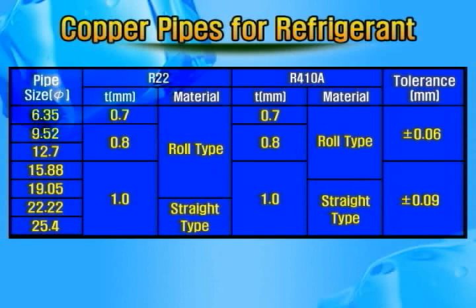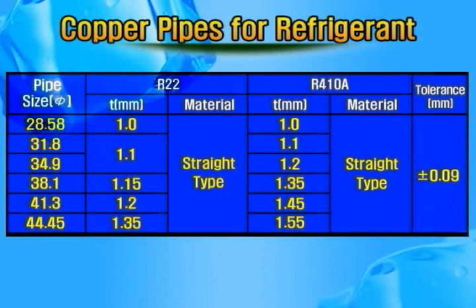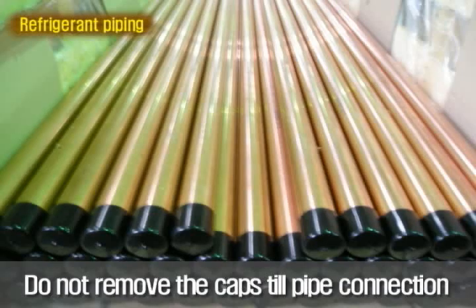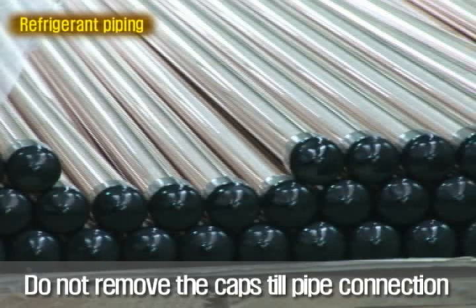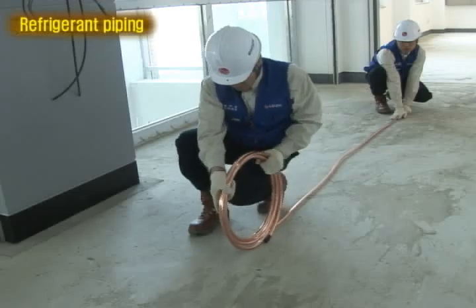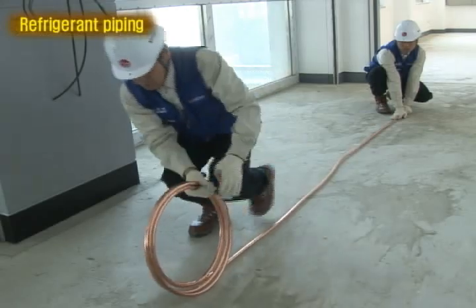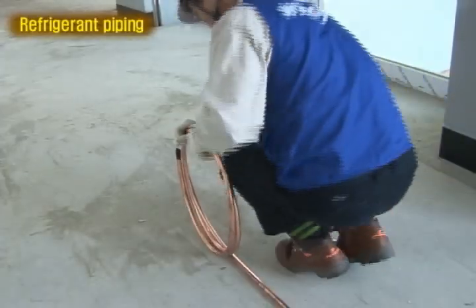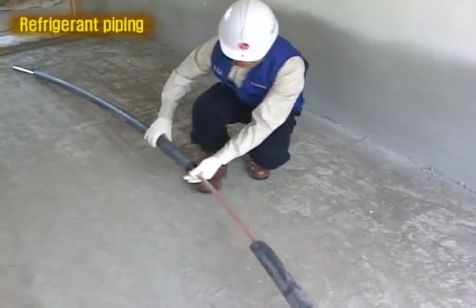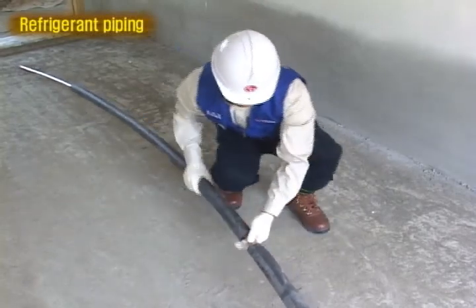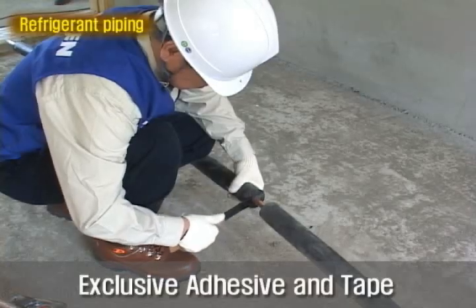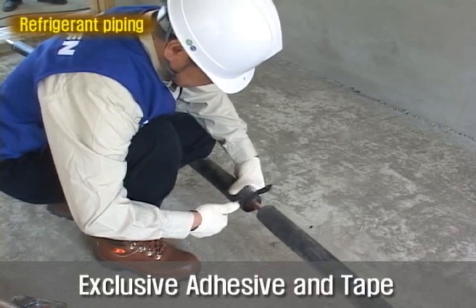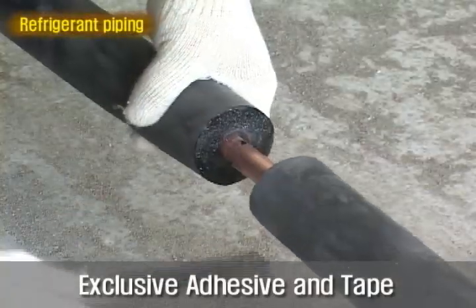Be careful, the copper pipe thickness differs depending on the refrigerant. Cover the pipe ends with caps to prevent foreign materials, and unfold pipes on a flat floor slowly to avoid crushing. Arrange insulation on the pipe so as not to make dew, and when you connect insulation, paint adhesive and use adhesive tape.